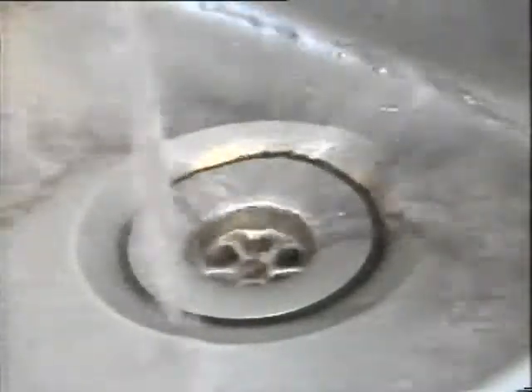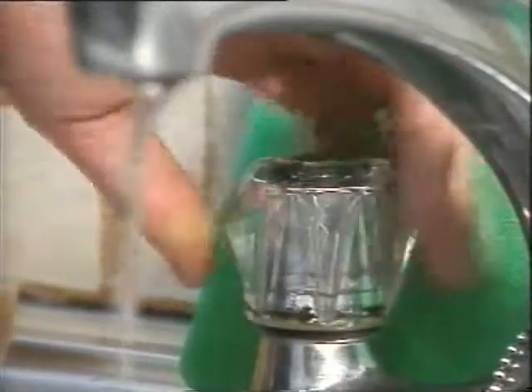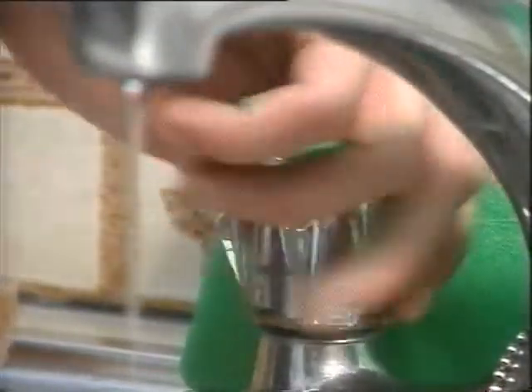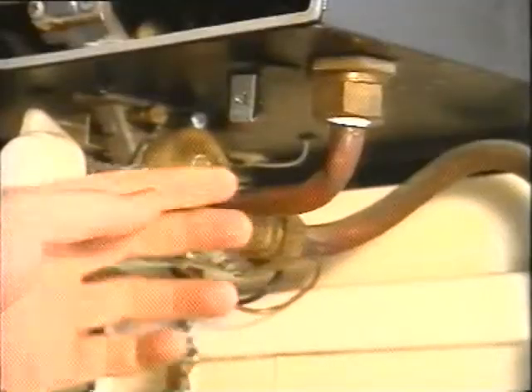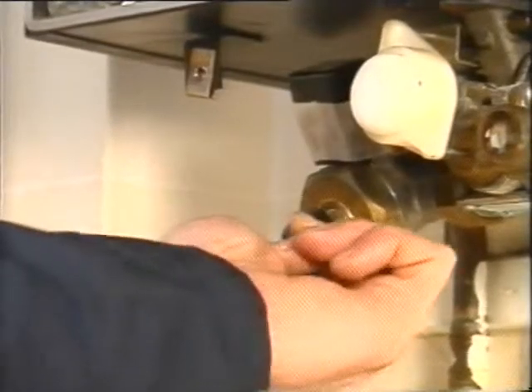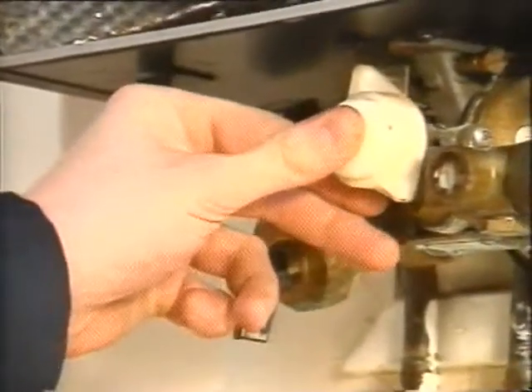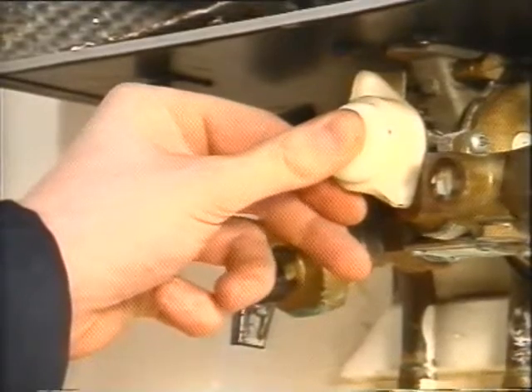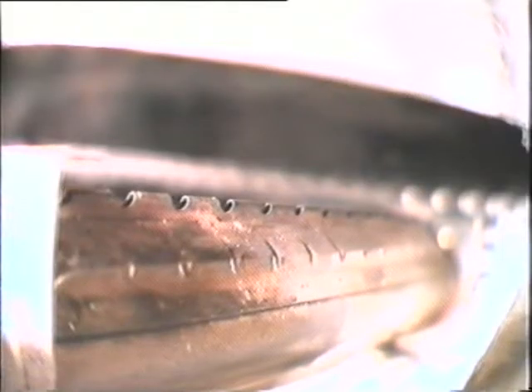Then turn on all the hot taps or the appliance outlet. Now turn on the water service cock, and when the water's flowing freely, turn off the taps or the appliance outlet. Turn the gas on. Check for water leaks, and if there are none, turn on the gas and light the pilot. Make sure the ignition device is working, and that the pilot flame's okay and set properly in order to heat the flame failure device. With the appliance set to main flame, turn on the hot tap.